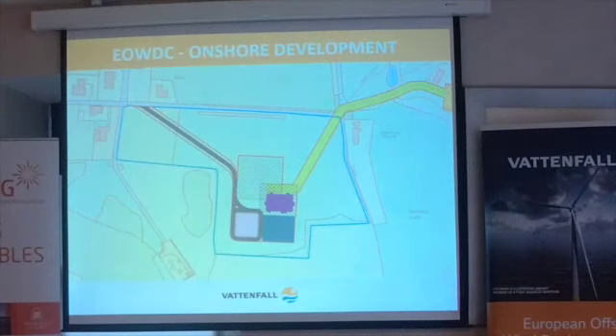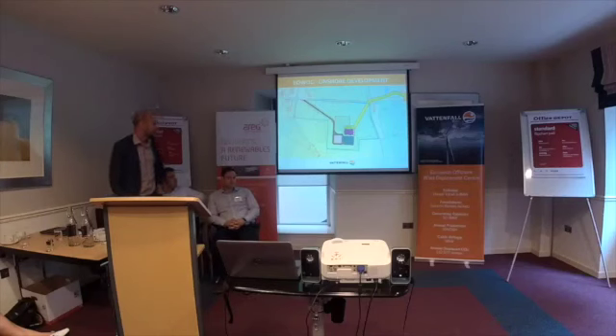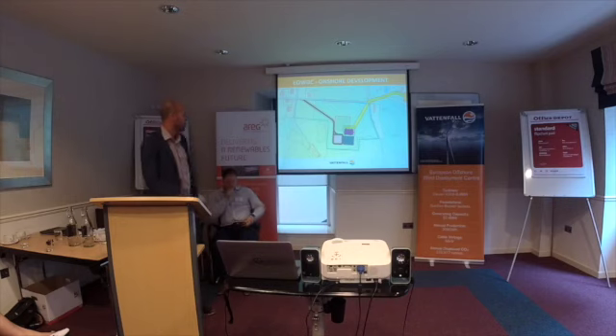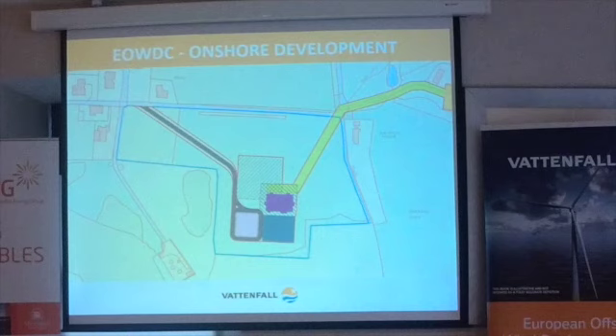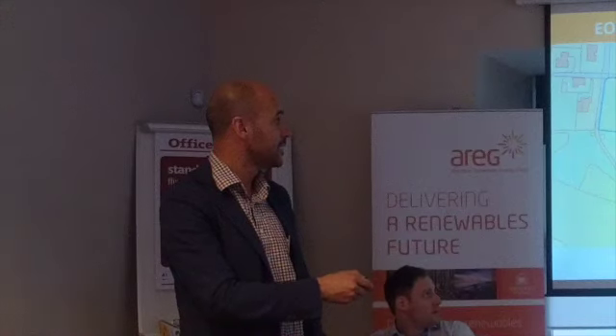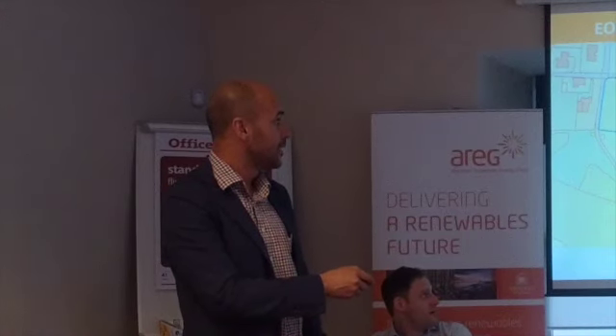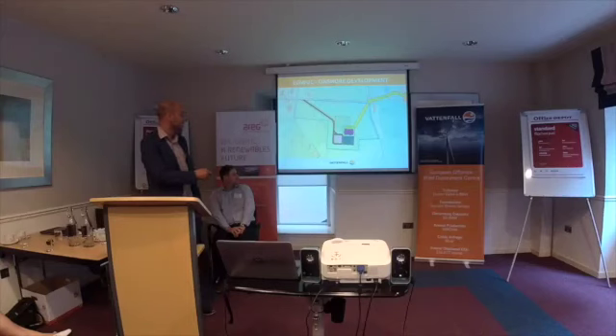That's a small overview of our substation site at Black Dog. We're building two facilities there: a 66 kV building, where the offshore export cables from the North Sea come into a transition pit. There's a short onshore cable route, and those 66 kV cables are terminated in this building into switch gears.